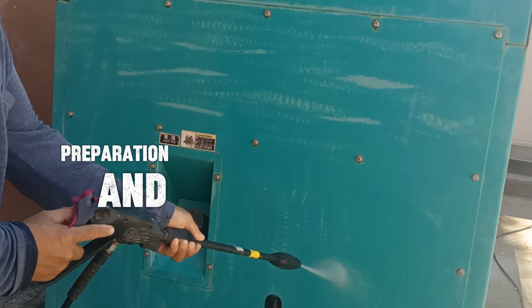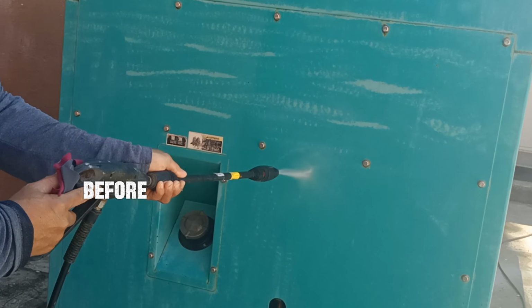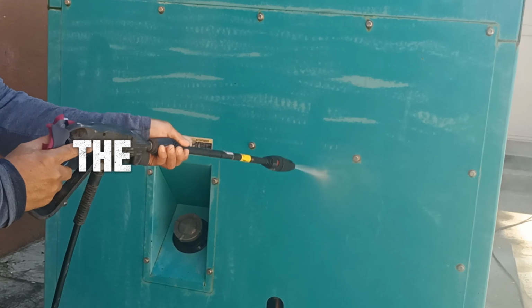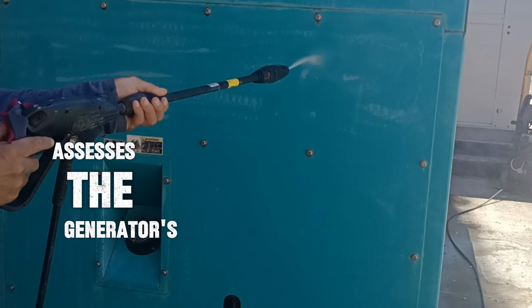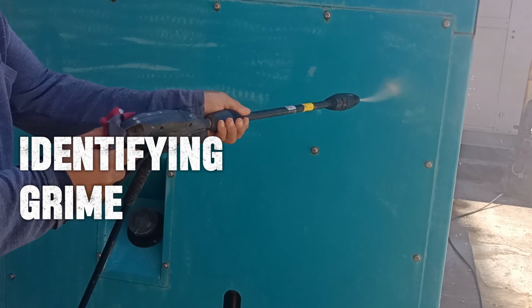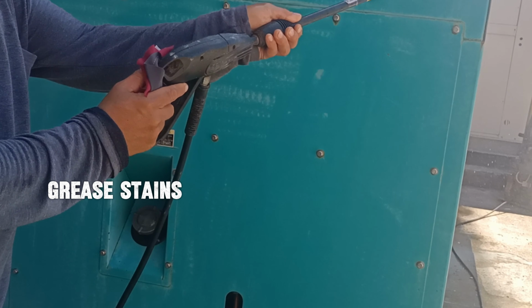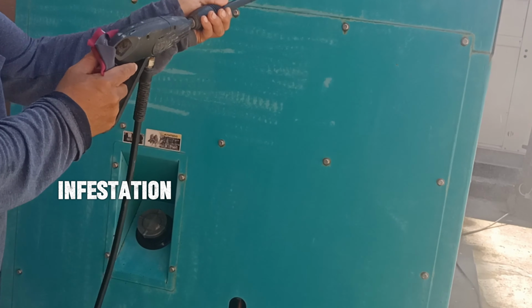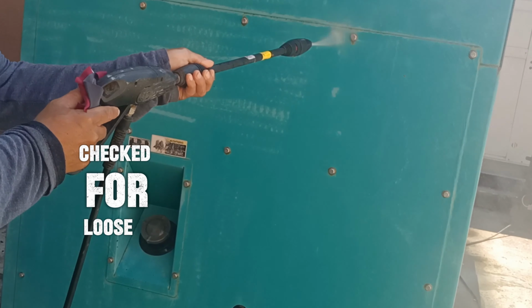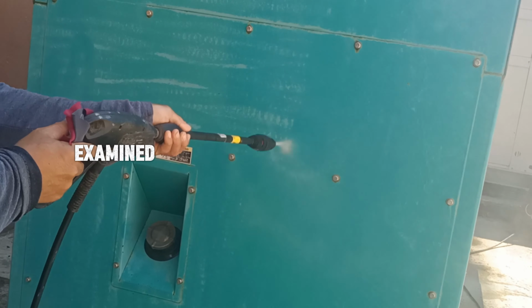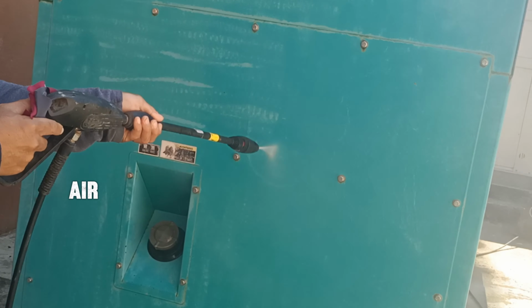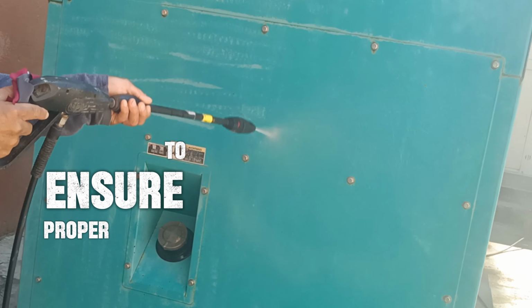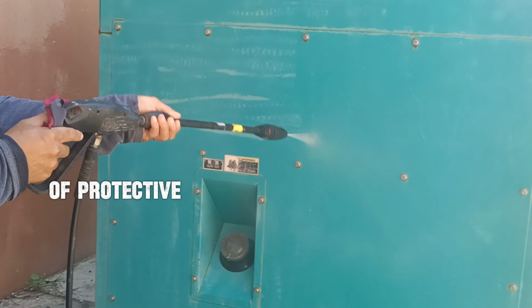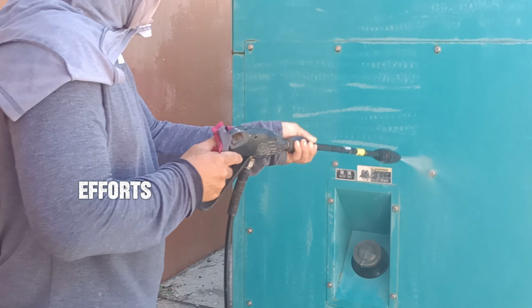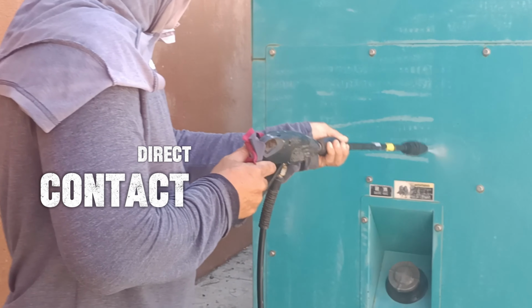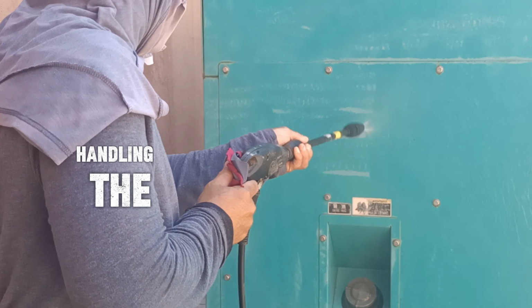Surface preparation and initial inspection. Before the washing process begins, the team carefully assesses the generator's condition, identifying grime accumulation, grease stains, and signs of pest infestation. Panels are checked for loose bolts, wiring connections are examined for rodent damage, and air vents are inspected to ensure proper airflow. Despite the lack of protective gear in this session, efforts are made to minimize direct contact with contaminants while handling the unit carefully.